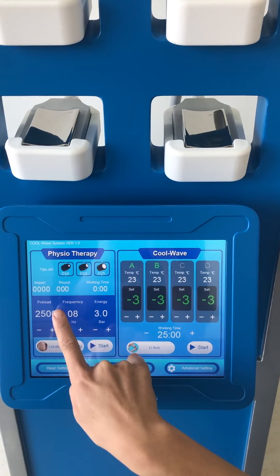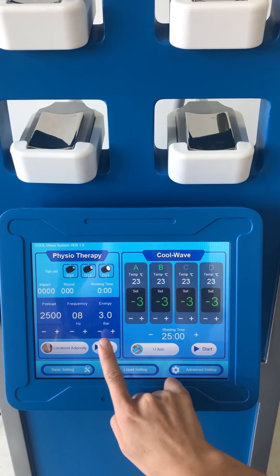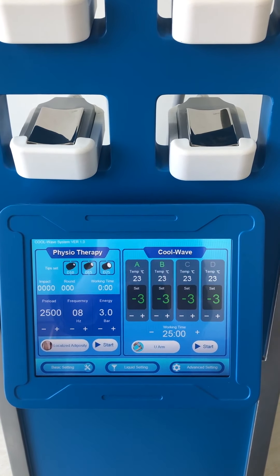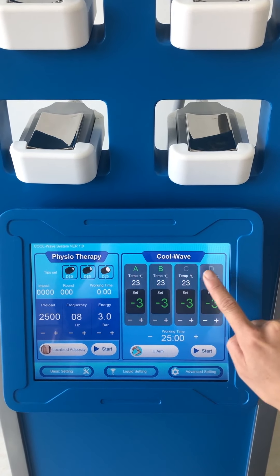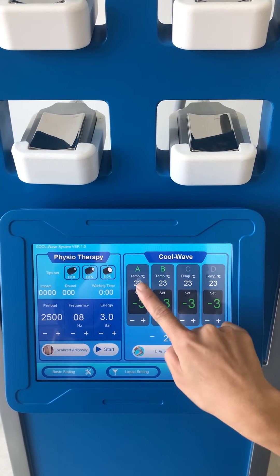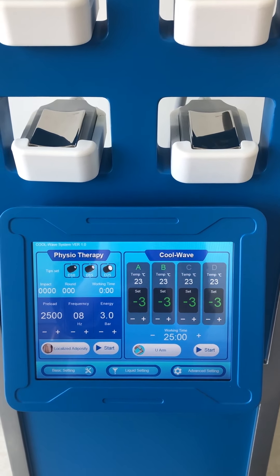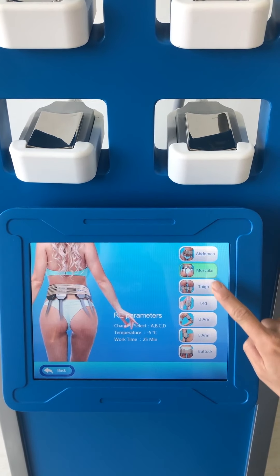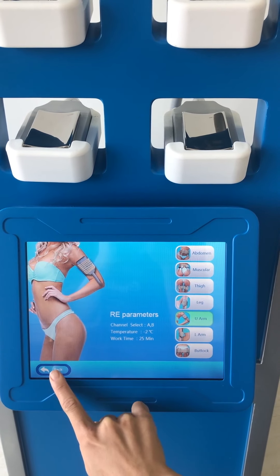After the preload, frequency and energy settings are the basic parameters needed before starting the treatment. In the Cool-Wave page, channels A to D clearly show the four cryo pad channels, displaying both the real temperature and the set temperature. There are also 7 body parts for selection — choose the cryo pads based on the size of the body part being treated.